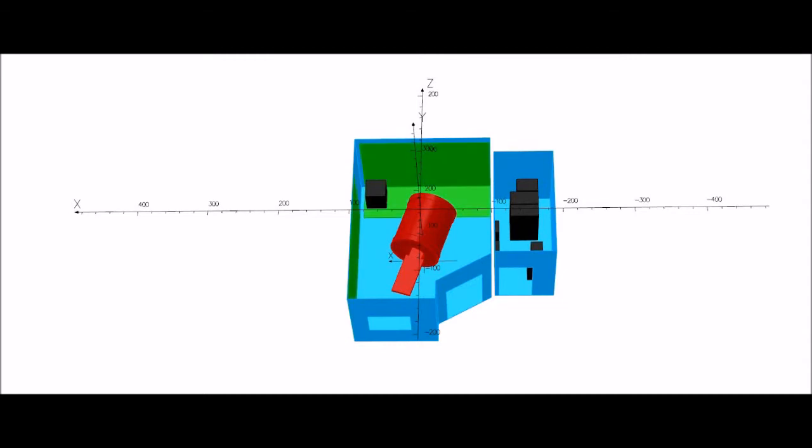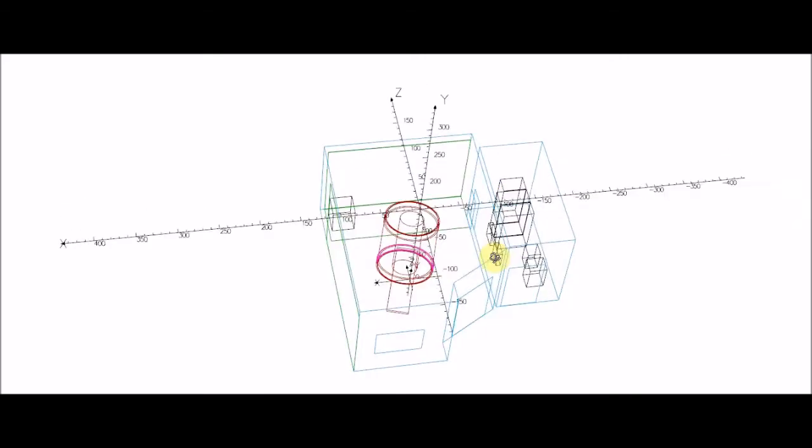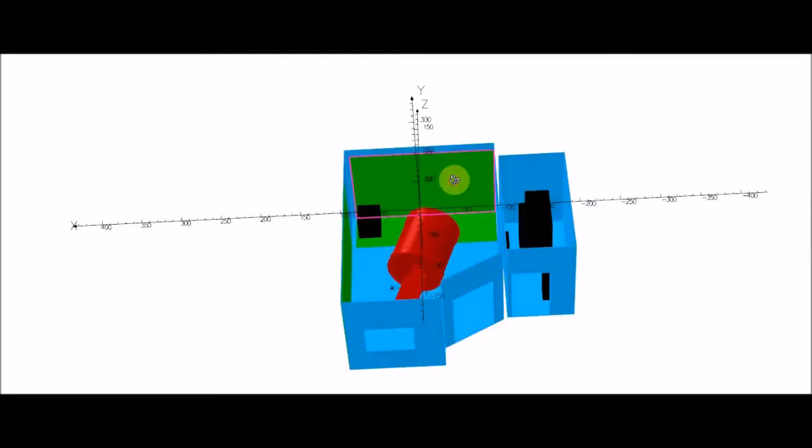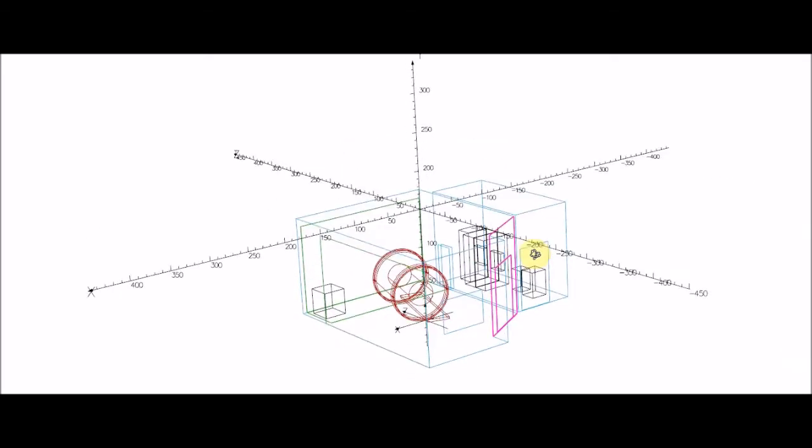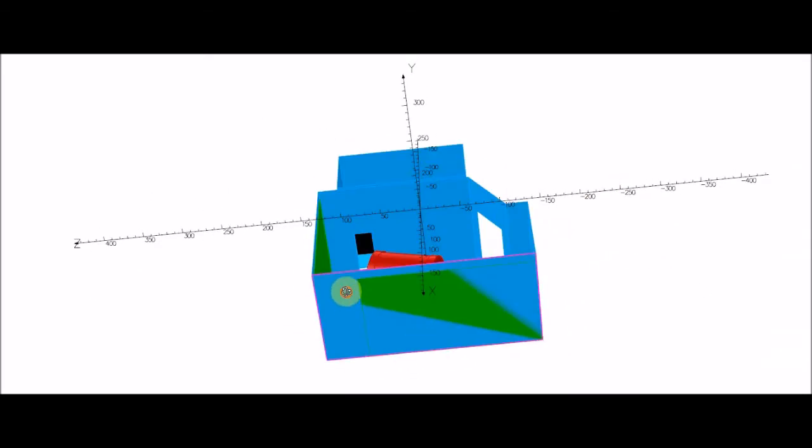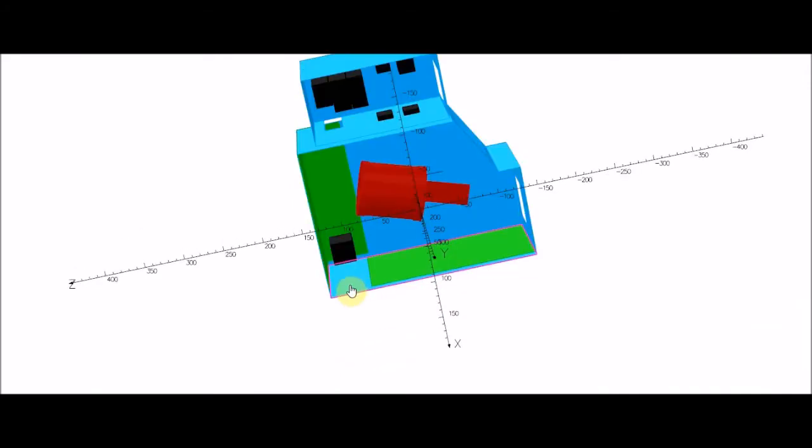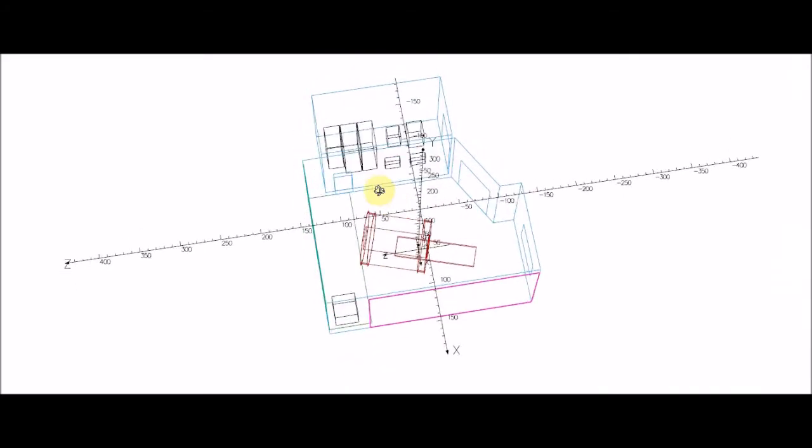And we use green just because that's kind of the default color that everyone uses for steel. This particular magnet, it's a 1.5 GE. So you needed steel on the back wall. And because of the angle, steel was not necessary as you can see here in this area. Because of the Gauss lines just don't go through there.